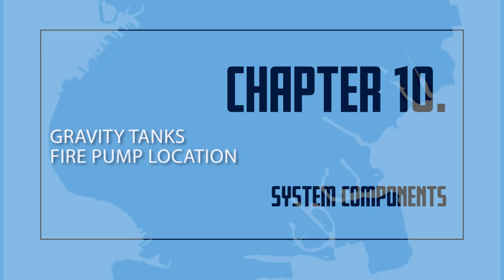Fire pump location. The fire pump should be housed in a room that is fire-resistant or constructed of non-combustible material. The pump room should be located as close as possible to the fire protection system. The pump room should be kept clean and accessible at all times. The fire pump, driver, and controller should be protected against possible interruption of service. The temperature inside the pump room should be maintained above 40 degrees Fahrenheit at all times to prevent freezing of the water. The pump room should only be used for fire protection functions and not for general plant operations. No storage is permitted in this room.